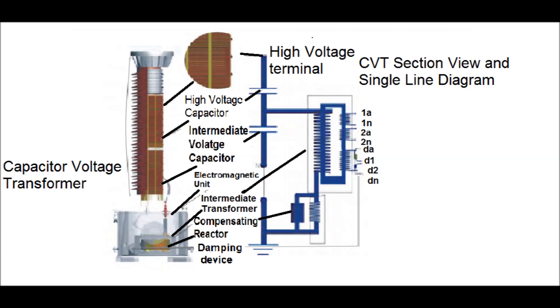The compensating reactor, the damping device, and terminals 1a, 1n, 2a, and 2n are the secondary terminals for the CVT. A damping device is introduced to nullify or reduce the ferroresonance problem in CCVT.